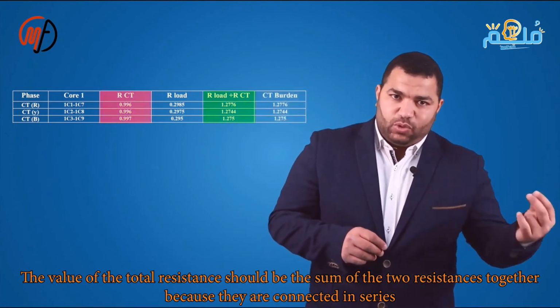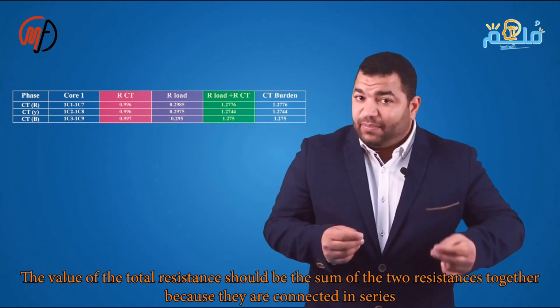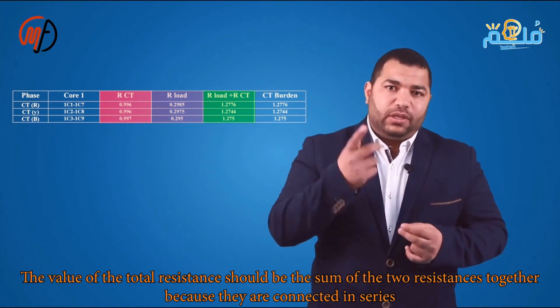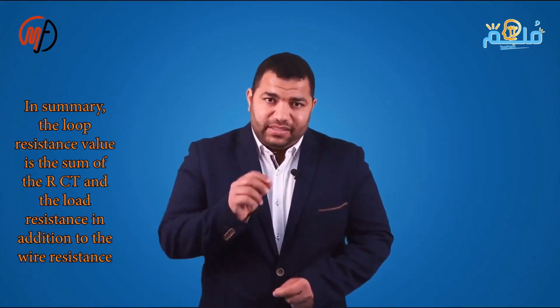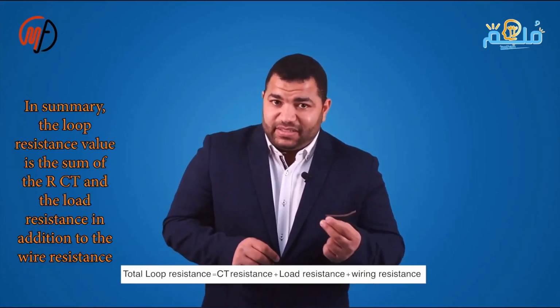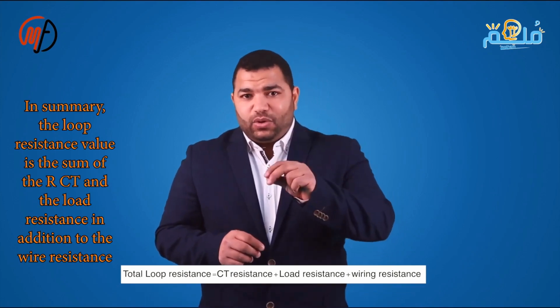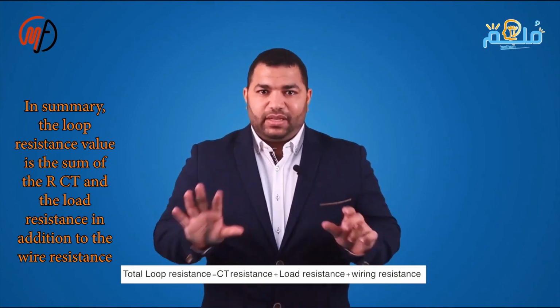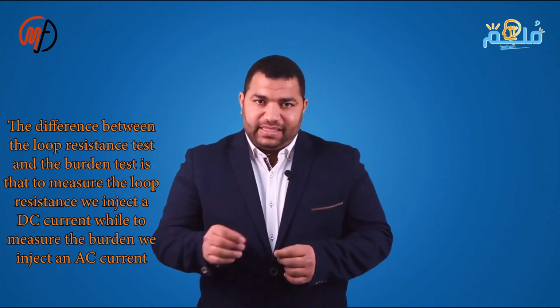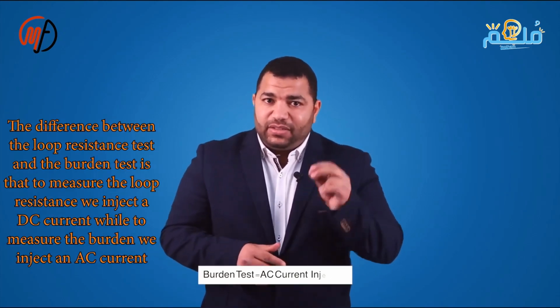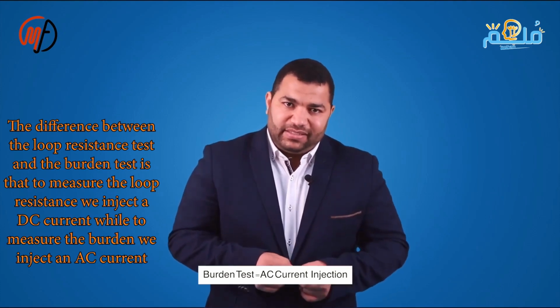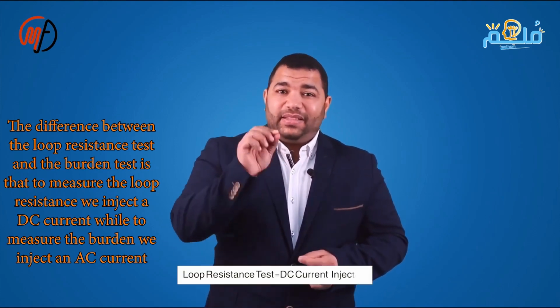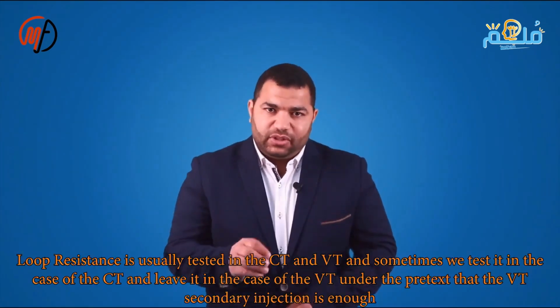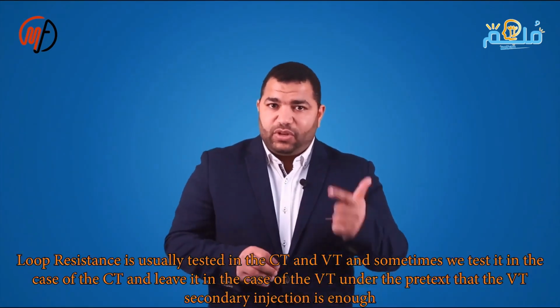The difference between measuring loop resistance and burden is the current type: AC for burden, DC for loop resistance. Loop resistance is typically tested for CTs and VTs, but often skipped for VTs if VT secondary injection suffices. Test for a single earthing point for each CT loop to prevent circulating current. Ensure one earthing point per CT loop.